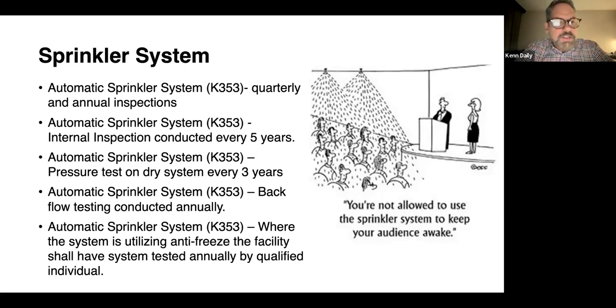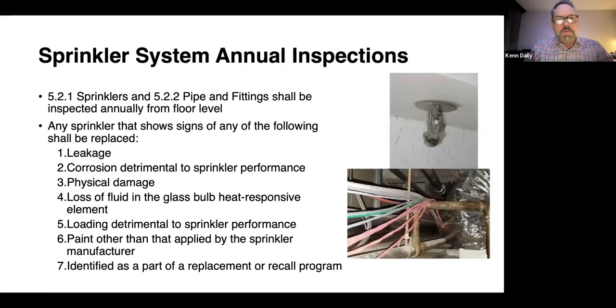Backflow testing, as I said earlier, is done annually. Every sprinkler system does have at least one, if not more, backflow devices that are tested. And then antifreeze testing, where it's used, is tested on an annual basis. Again, it must be done by a qualified individual. One of the things I want you to be doing, because it's required, is documenting your annual inspection. So, for instance, that picture on the top there, dirty heads. You need to be looking for all the heads that have dirt, grime, buildup, rust, corrosion. That's on the head itself, or even the escutcheon around it.